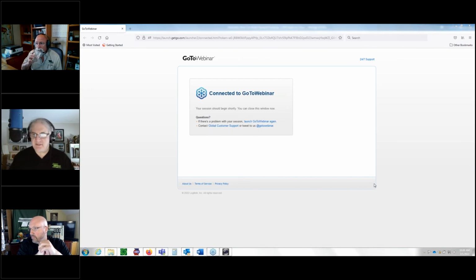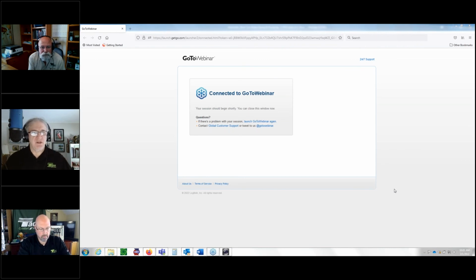There are a couple of questions that came up during the presentation that I wanted to address specifically that weren't part of the presentation. One was, would you recommend hydraulic separators instead of closely spaced tees? And the answer I wrote to Brian, who asked the question, was it depends, right? It depends on the size of the zones that you're dealing with. If it's just a single big zone or just a handful of zones where the BTU load of the zones are larger than the lowest firing rate of the boiler, closely spaced tees are fine, and that covers an awful lot of your jobs, right? So that makes closely spaced tees your go-to method for ModCon boiler piping.